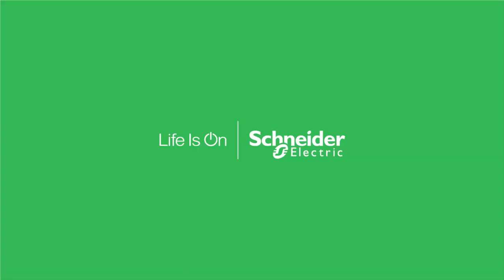Okay, so at first when you started the question, I was thinking on the high end, and now I know that they're probably talking about the low end, so I'll address both. So normally, for many meters, you have a minimum amount of current that it needs to detect, remembering that you have a system where you are using current transformers, generally 0 to 5 amp, and you are measuring the current and trying to have an output that represents that from 0 to 5 amp. So if you have a 1,000 amp CT, it's not unusual that below 5 amps, it's very hard for the meter to detect that and be able to measure that accurately. So generally, some people even say 10%. I would say the accuracy below 10% loading can be an issue, certainly below 5%.